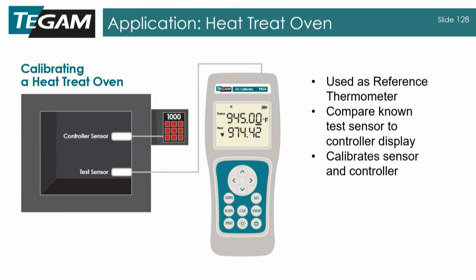Another way that calibration is done, this is in heat treating, so we do some work with people who are doing AMS 2750 heat treating for aerospace. So you've got a heat treating oven, this is a simplification of it, of course. You've got a controller here, and this is often a K sensor because of the high temperature operation, but then this sensor will be an N. I ignore this, that says K, that's not right, but this would typically be an N sensor because N tends to be more stable and exposed to higher temperatures.